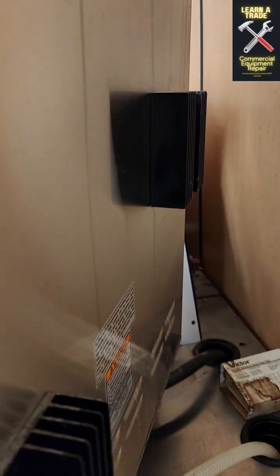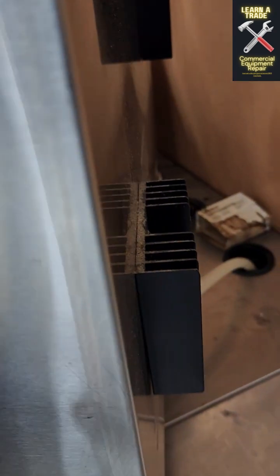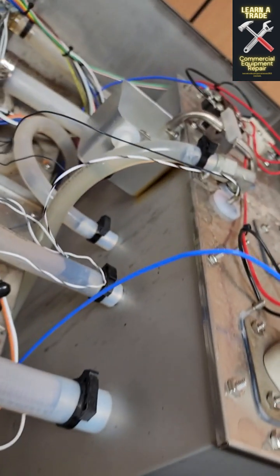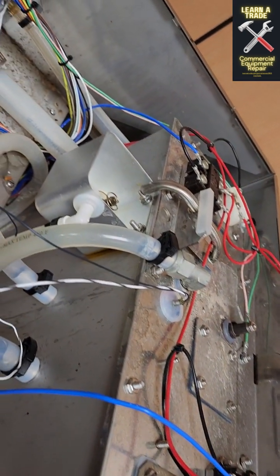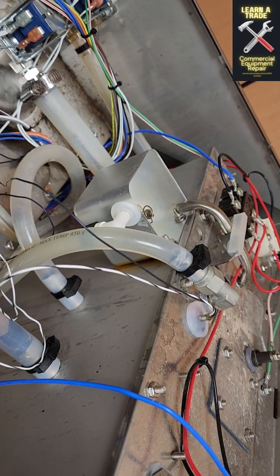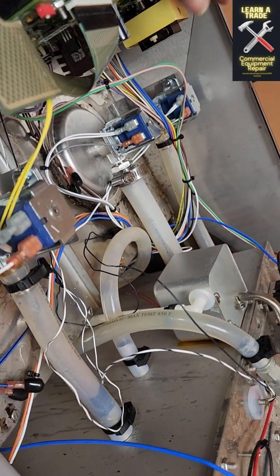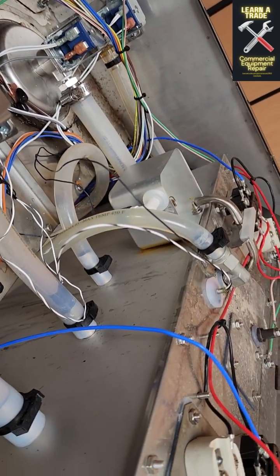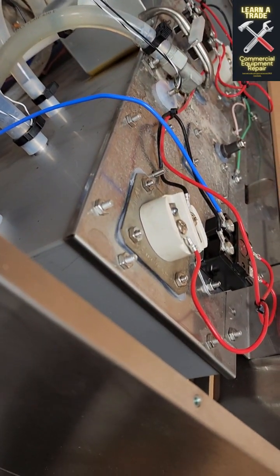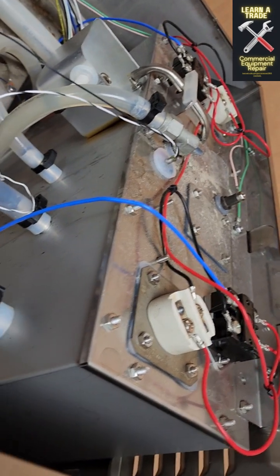So what I'm going to be doing is getting this disassembled, and then I'm going to replace the Triacs, power it back up, and see if that takes care of the problem. Usually that is the issue. From everything they said they replaced, that's pretty much the final component that would cause this overheating issue.